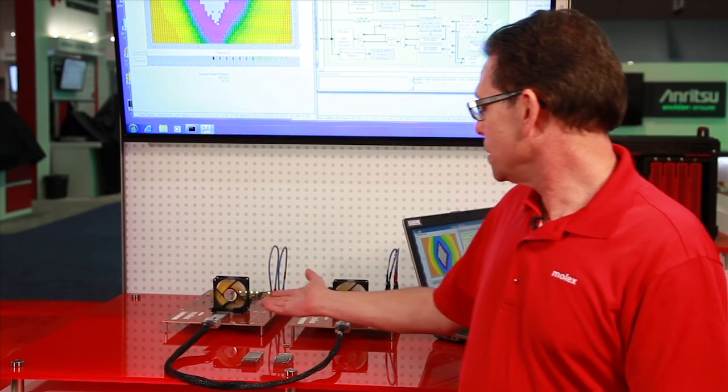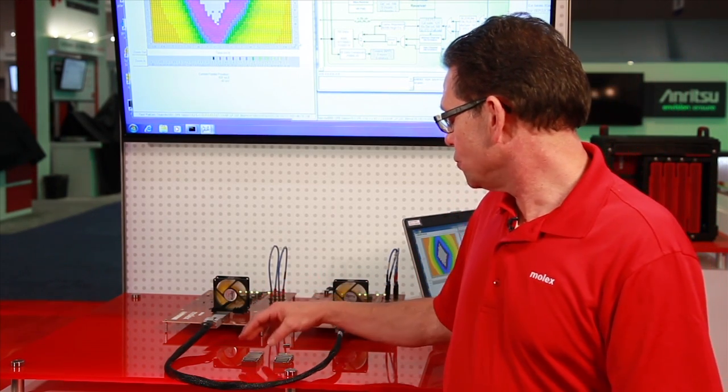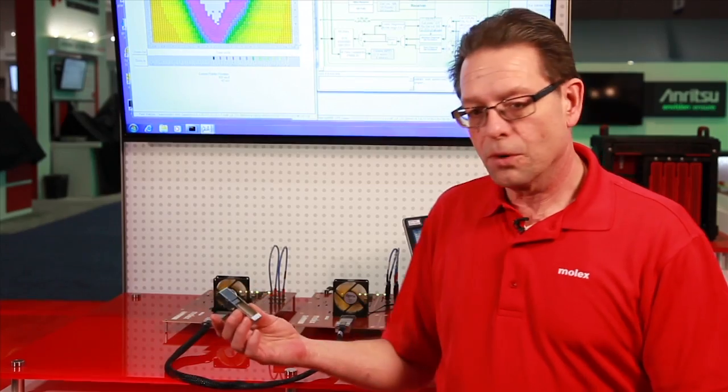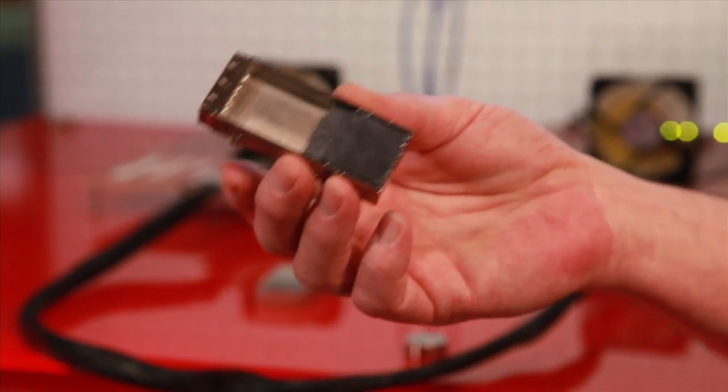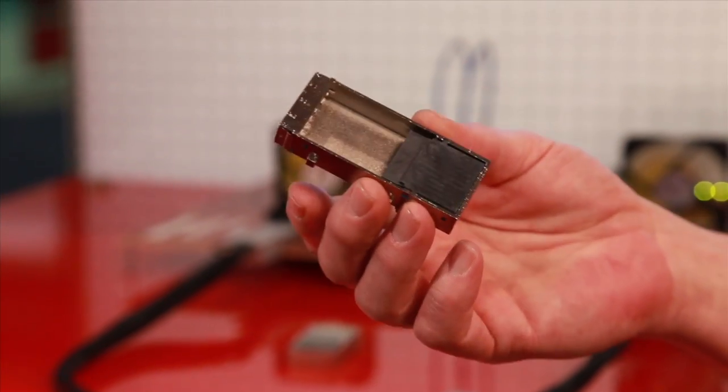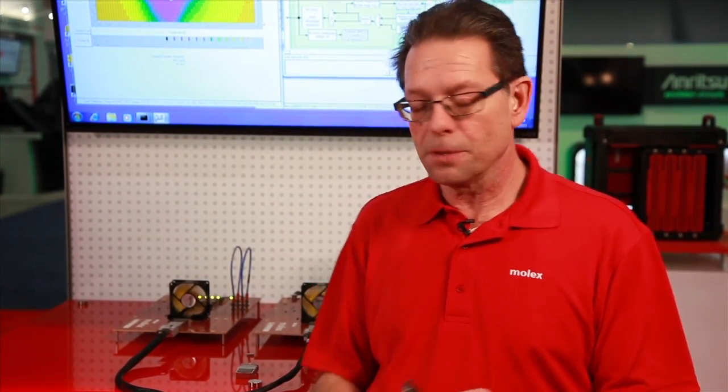The connector basically comes in two versions. We have what is called version 2 in the CDFP MSA. This is a longer version of the product and it's really used to implement AOCs and optical modules. The reason the connector has been lengthened is to provide for more effective thermal management by using heat sinks that are larger to manage the thermal output of the AOCs and the various types of optical modules that can be implemented.